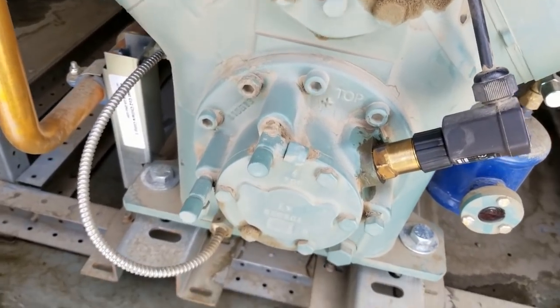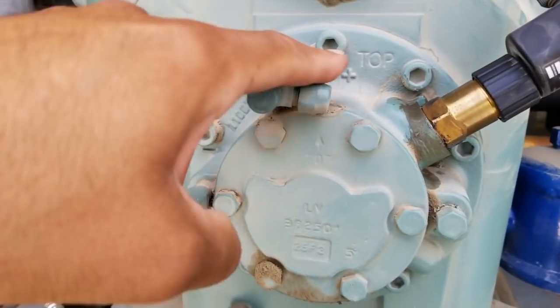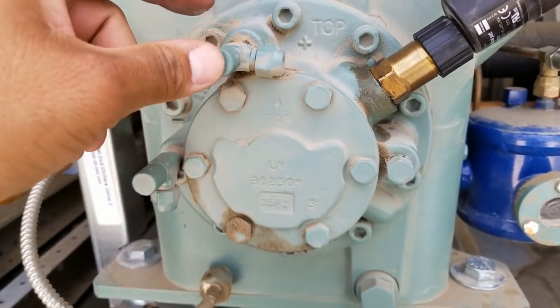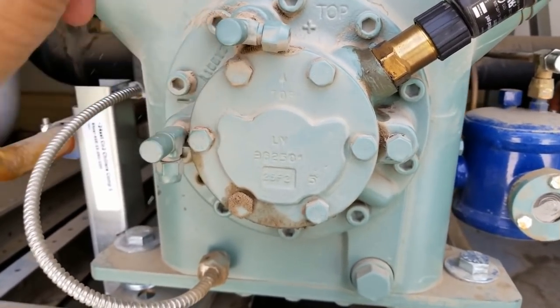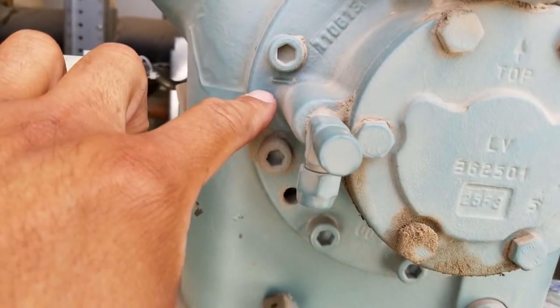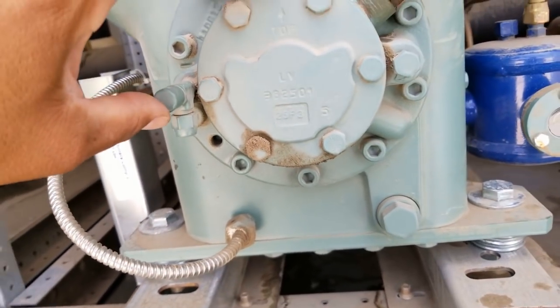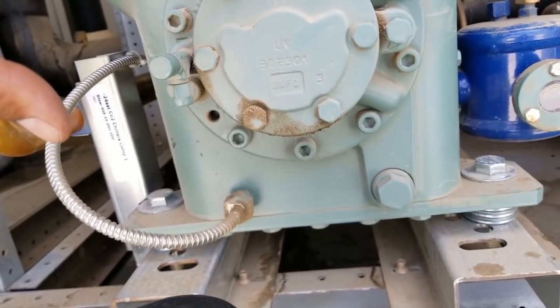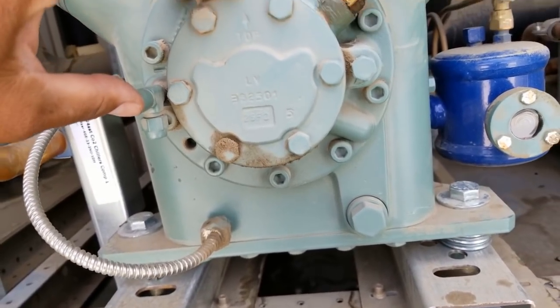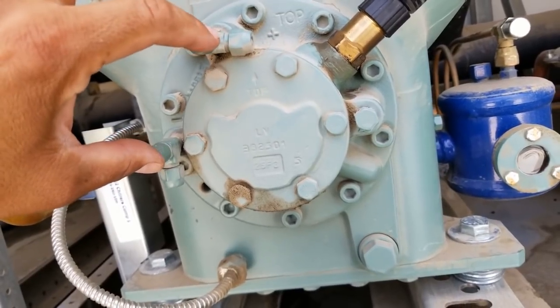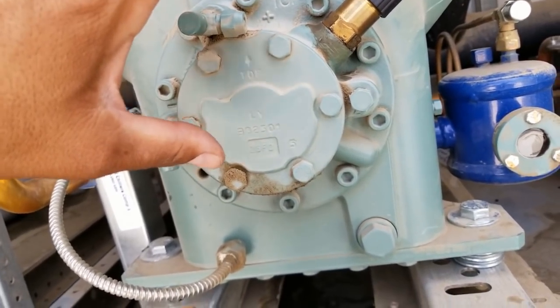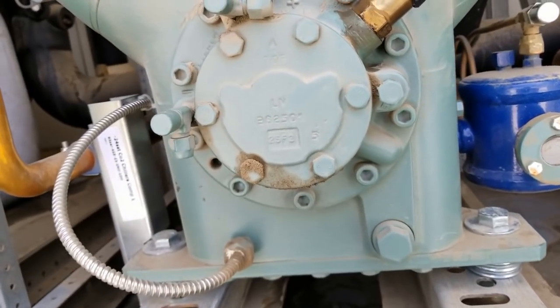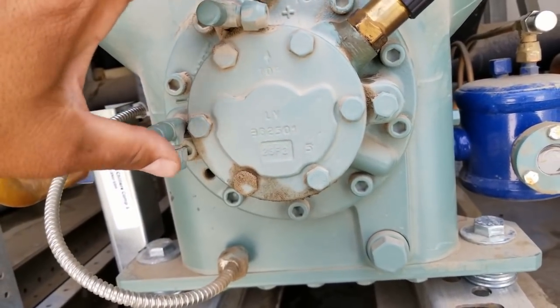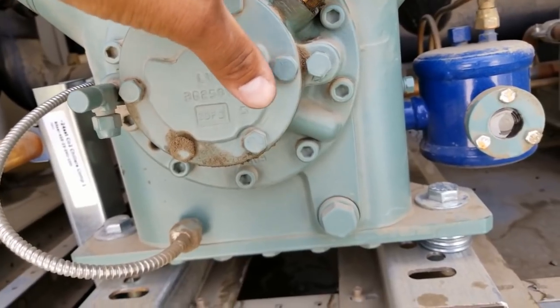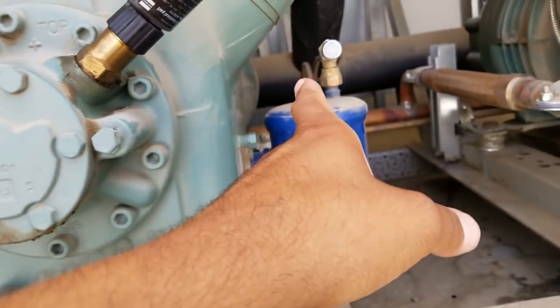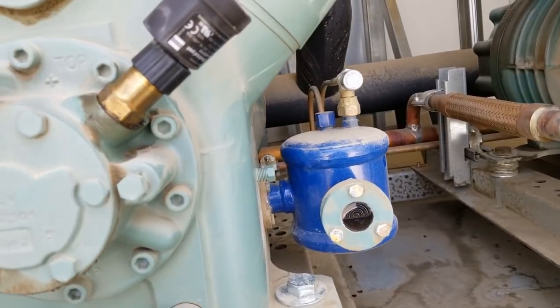On the top one here you've got your little plus. This plus, you put your gauge on here, and the minus right here, you put your gauge on here, and that's where you'd get your differential on these two gauges to see exactly where we're at. So if we're within the 20 to 50 range, this is doing good. But if not, there's some issues going on in here, which is probably my flood back. So this is the first time it happened.